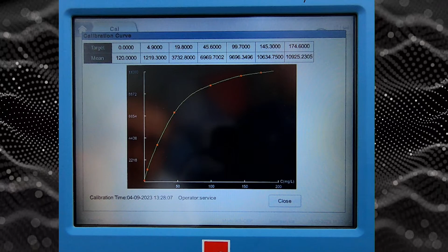Here we have the calibration menu, and in calibration we have the CRP gain calibration. This is the menu which I was showing you before. In order to make this calibration you just need to make 6 blank measurements, and then if the conclusion is passed you need to save it, and this will be the new reference. Then you can go to calibration. As you can see, we have 6 levels of calibration, the calibrators. It is a spline type reaction, with targets for each concentration, and according to this the calibration curve is calculated by the analyzer.